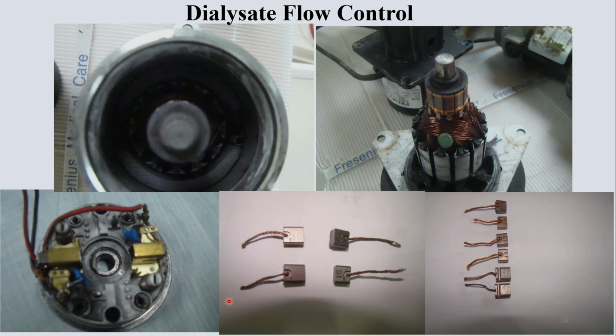And over a period of time, this is what will happen when you use it. That carbon is continuously shaved due to the contact of the brush with the rotor of the motor, and it will accumulate over here, and eventually it will obstruct the rotation of the motor, in which case the base of that needs to be cleaned with a dry brush and those carbon fines removed.